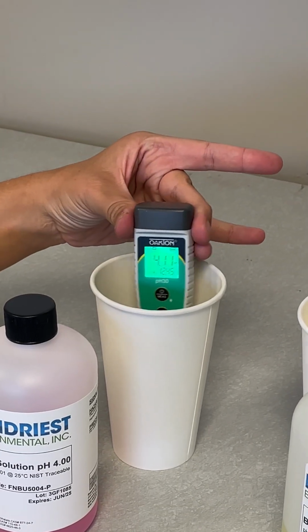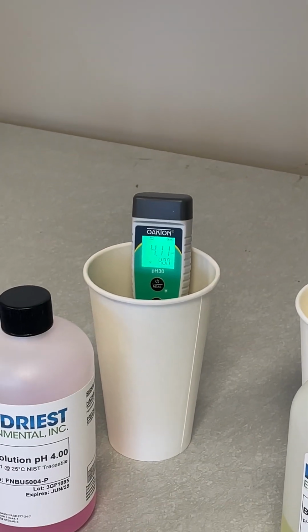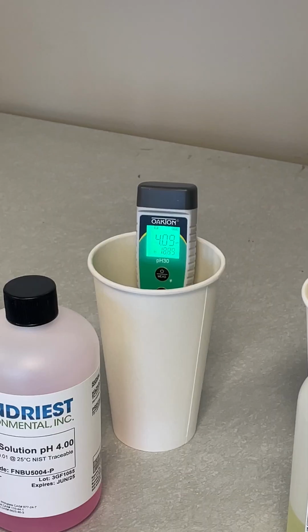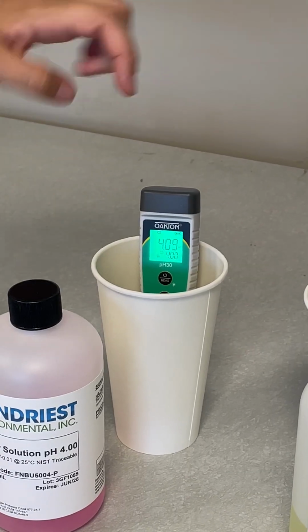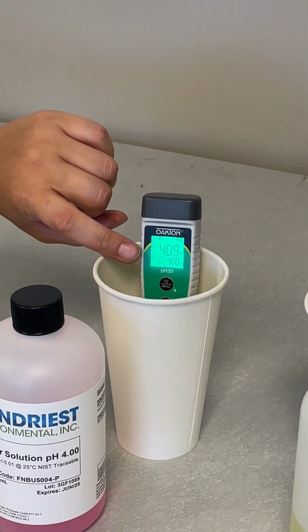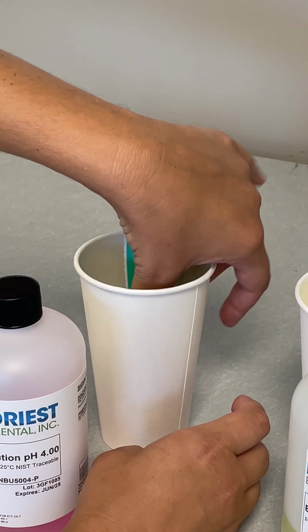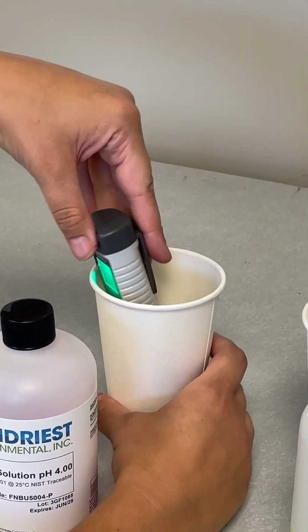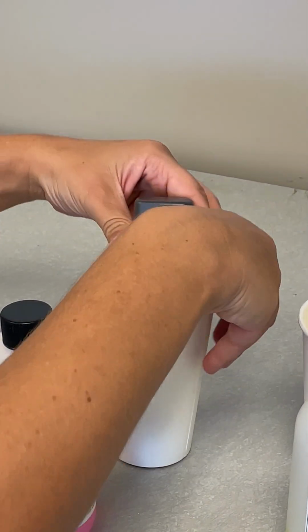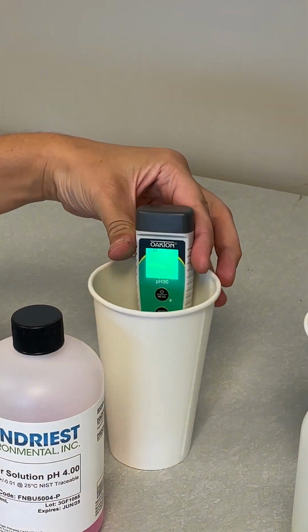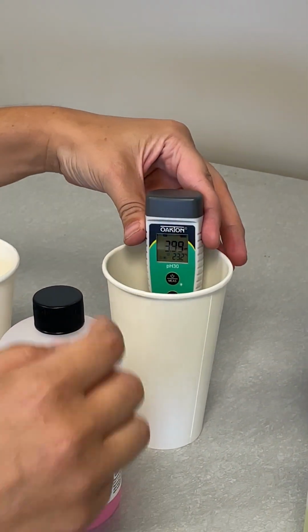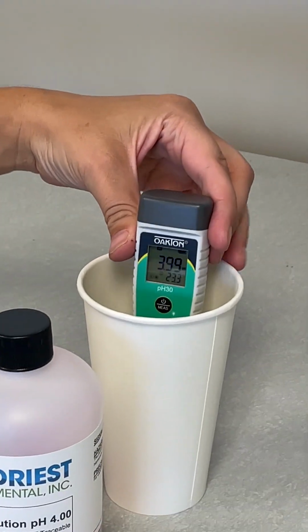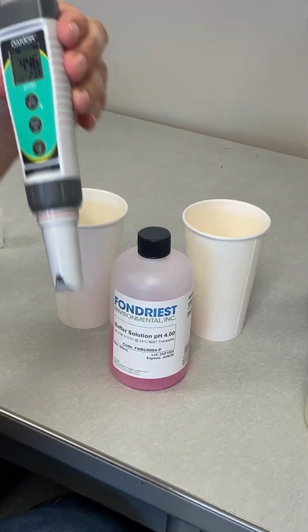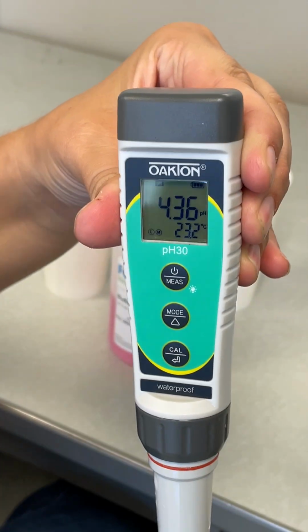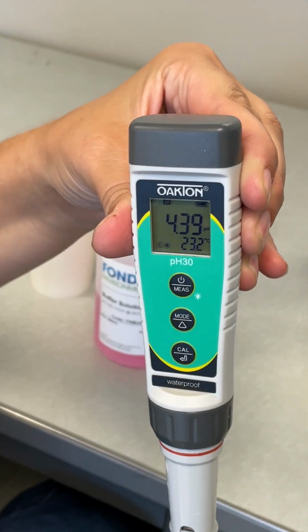Sometimes if you swish it around a little bit, it helps go a little faster. Okay, so the meter knows it's on 4. It has a smiley face, so I'm gonna short press that calibrate again. Oop, I didn't do it. Still lit up, so you know I didn't hit it. Okay, now it'll blink. And I'll write this 3.99 down on my Form A. I'm not sure if you can see it when it's not lit up, but there's an L and an M so far. It means I have calibrated for our middle point and our low point.